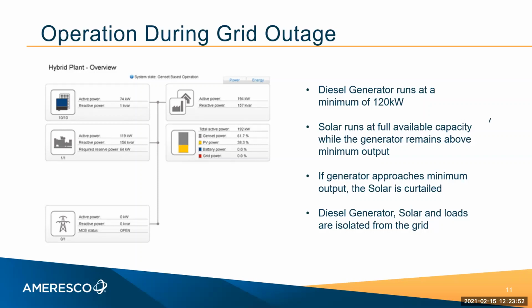If the solar array plus that minimum 120 wasn't enough to feed the building, then the generator would ramp up accordingly through frequency control. And if the generator dropped to 120 and the loads continued to be reduced, then the solar array would be actively curtailed by the fuel save controller to prevent the generator from dropping below its minimum set point. In this particular situation, again, this is during commissioning, and you'll notice in the bottom left, there's no power from the grid, and the main circuit breaker status is open, meaning it's disconnected from the grid.